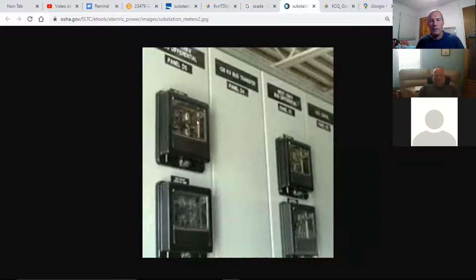And if you had phase relays, these are stacked up and down instead of side to side. You had phase relays, so you're able to get information off these relays just by looking at them. Like I said, electromechanical. They do have a little window in them, and they have an I and a T target, so you can see what kind of operations that you had. And if you need to disable a relay, there's got some knobs on it right here. You just pulled the cover off and pulled the relay out. That's not a very smart thing to do.